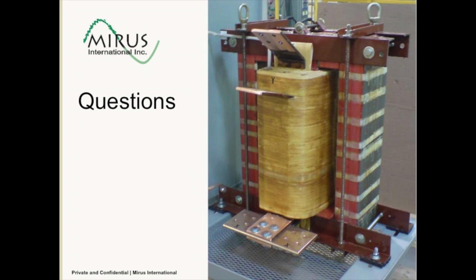We don't have access. The challenge is trying to determine what the voltage levels will be, and it's even challenging for generator manufacturers to figure out exactly what the common mode voltage is, the common mode voltage that's driving that circulating current, to figure out what exactly that voltage is. But generator manufacturers do try to predict that. If we could have access to that spreadsheet, then we could insert our impedance in there and do that calculation. So it is possible.